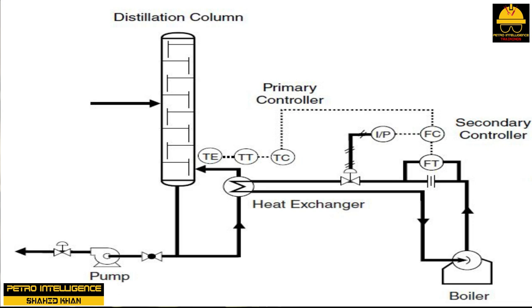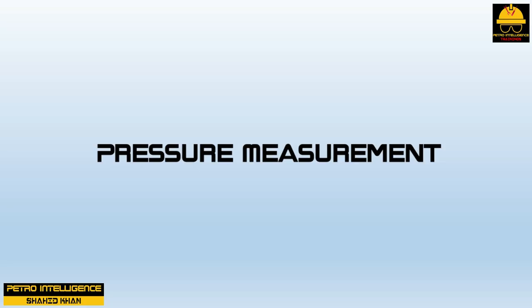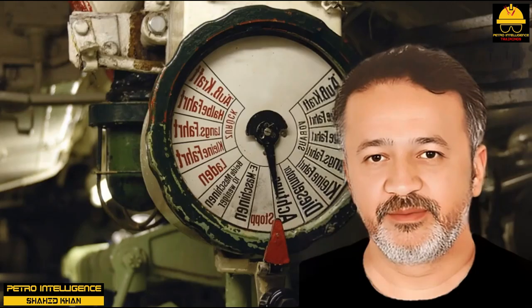Controllers are designed to initiate a change to return a process to a set point if a variance exists; they may be located in the field or in a remote location. The controller sends an electric signal to a transducer, typically located near the valve to eliminate process lag. The transducer converts the electric signal to a pneumatic signal of 3 to 15 PSI. The control valve then opens and closes depending on the signal, reducing or increasing fuel flow to the burners to control temperature.